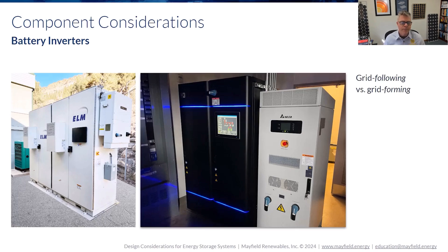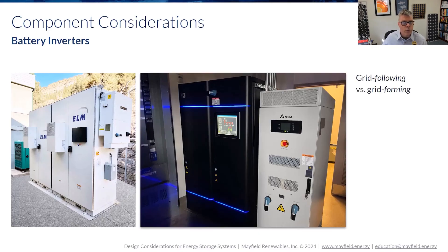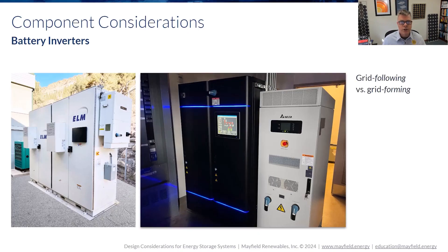Grid following versus grid forming is an important aspect of understanding what your inverter can actually do. Grid following means exactly what it says — it follows the grid, mimicking whatever the utility provides. This is what happens with grid-direct inverters; those inverters cannot create their own sine wave and can only follow what the grid supplies. We do have battery systems that are grid following, and they're only there to provide grid support services like demand charge management or energy arbitrage.